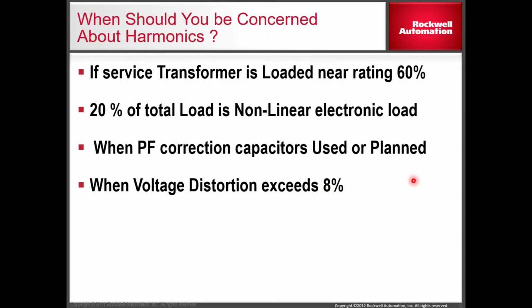So like we showed at the beginning of this presentation, if you have too much harmonics in your system, your transformers are going to start to overheat and become less productive and efficient, which then leads you to have to either add more distribution transformers, a bigger distribution transformer, or better yet, what if you just could reduce the harmonic content in your plant and save yourself the additional utility costs of installing bigger transformers? Well, the rule of thumb is once you start exceeding 20% of your total load capacity as nonlinear, you should start looking at the harmonics being produced and how to mitigate them.